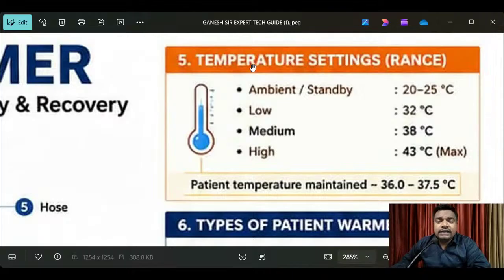I'm going to show you the temperature settings range. See here, patient warmer minimum. These are the basic parameters you have to keep in your mind when you are facing interviews. Based on your questions, the experts will ask you in this way, because I am one of the interviewers, and I have interviewed many engineers to confirm employees. Okay, and ambient or standby: see here, 20 to 25 degrees. Low, see here, 32 degrees, medium 38 degrees, and high 43 degrees maximum.